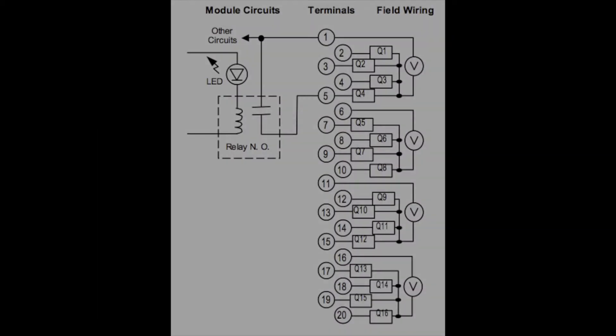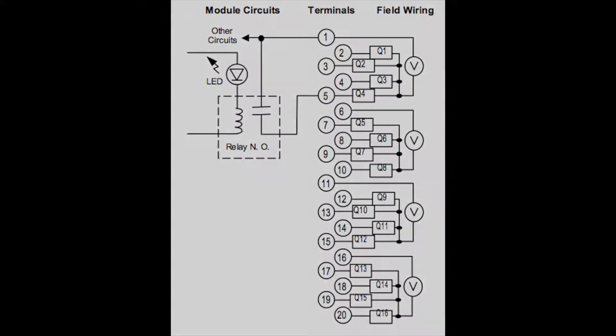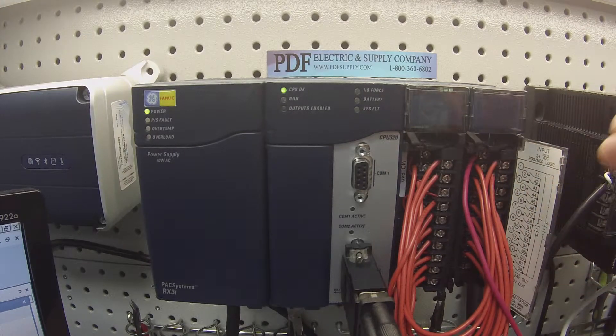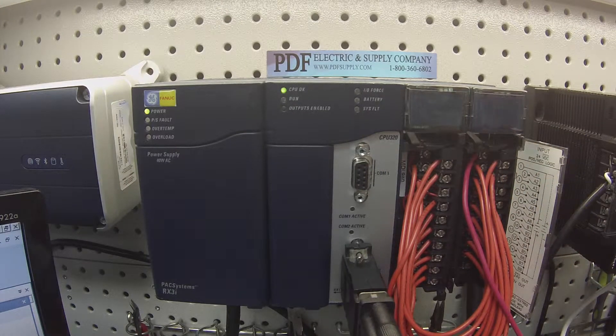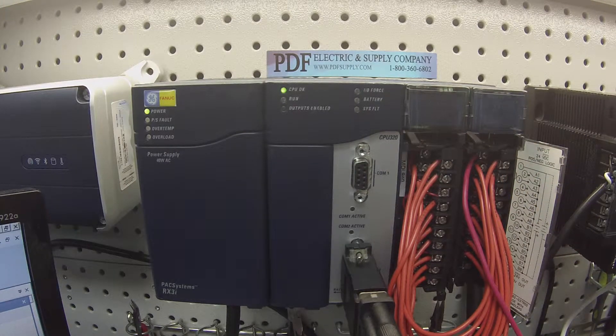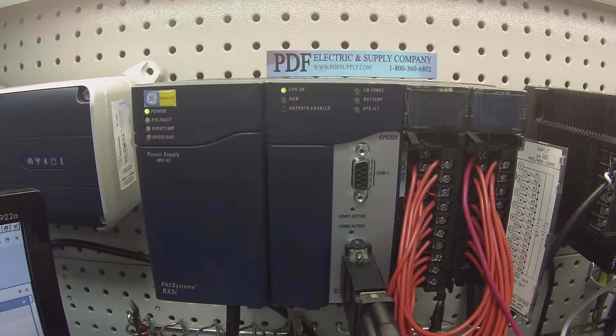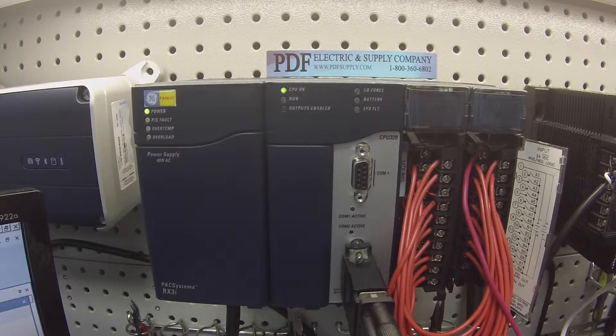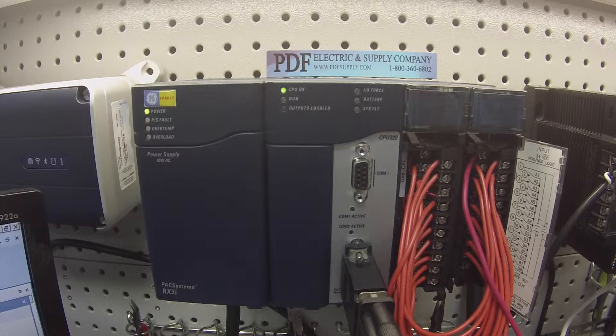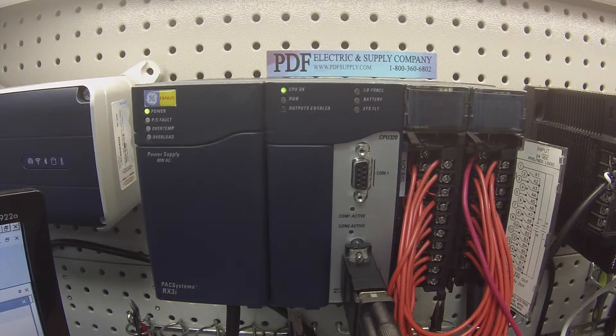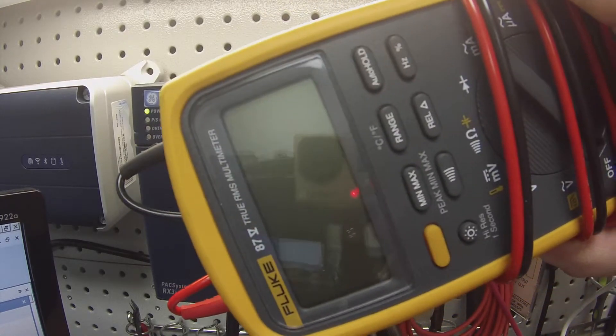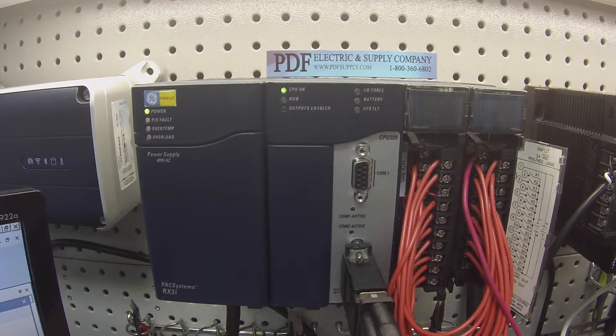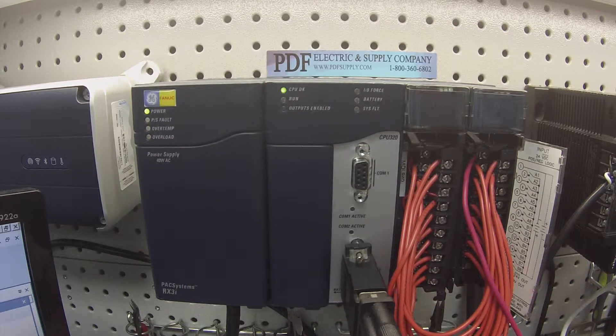It's set up into four groups and you put voltage positive where it's located, which would be screws 1, 6, 11 and 16. The negative you can actually just leave loose and you can touch each terminal with either a 24 volt relay so you can hear it clicking on and off, or a 24 volt bulb so you can see the light lighting up, or you can even use a multimeter like I have here, a Fluke multimeter that's reading 24 volt DC or as close to it as possible.